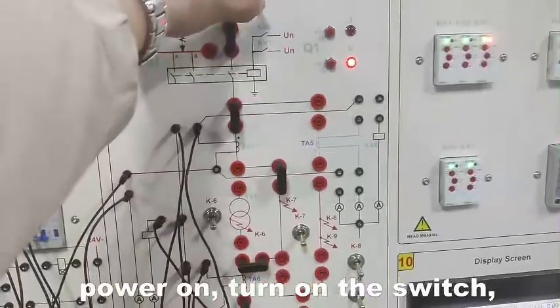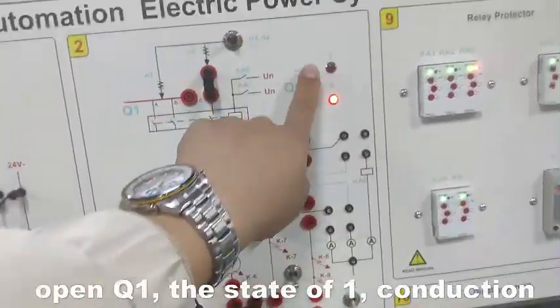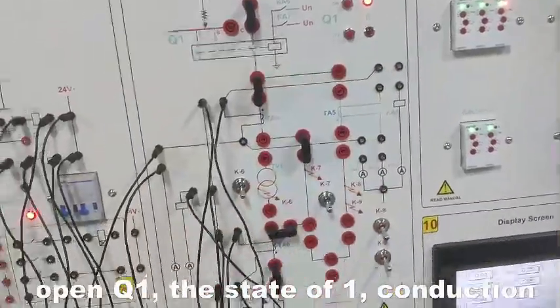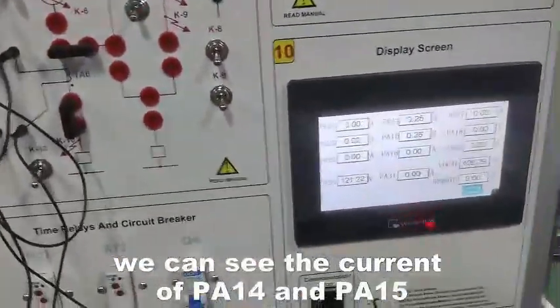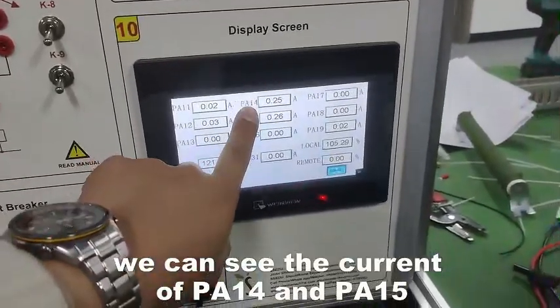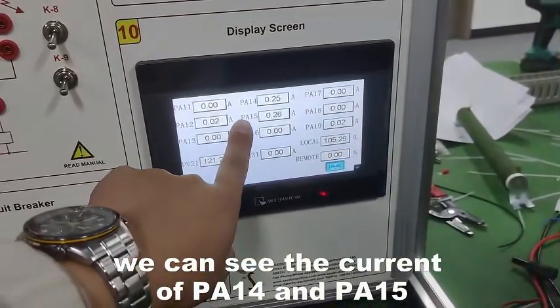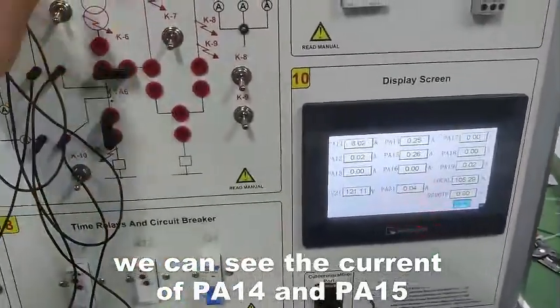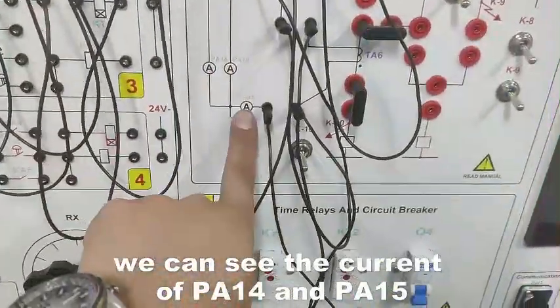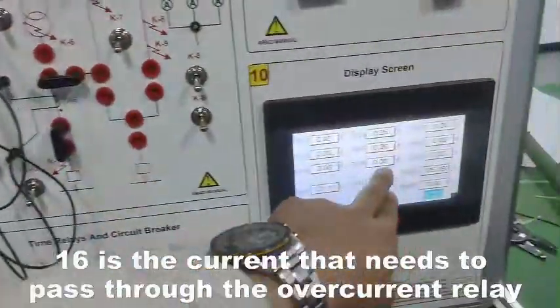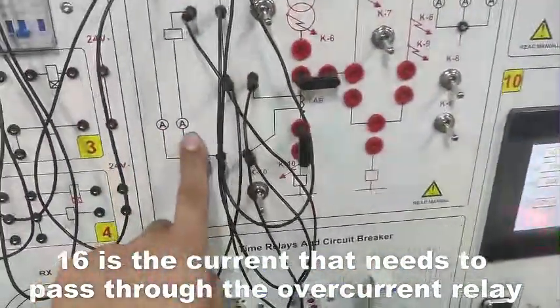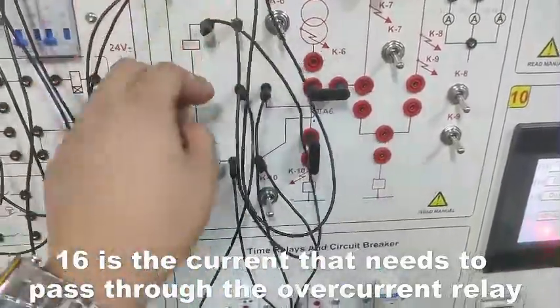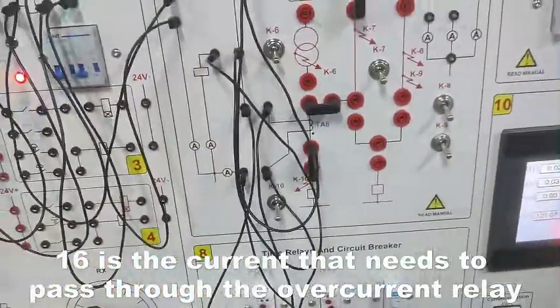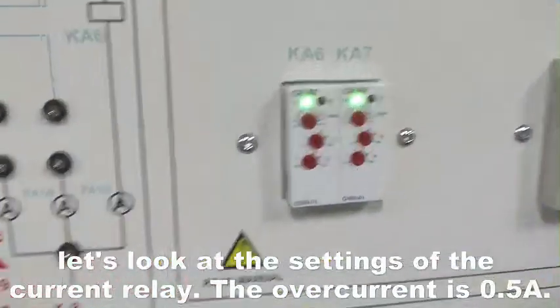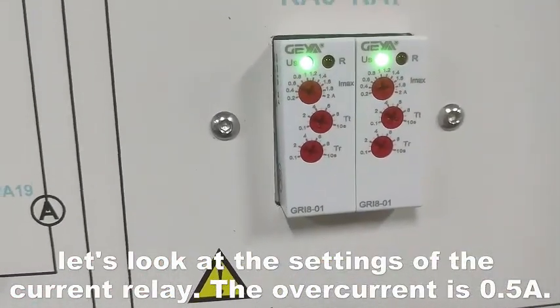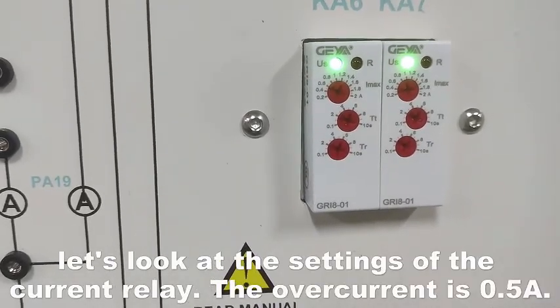Power on, turn on the switch. Open Q1, the state of Q1, conduction. We can see the current of PA14 and PA15. Sixteen is the current that needs to pass through the overcurrent relay. Let's look at the settings of the current relay. The overcurrent is 0.5 ampere.